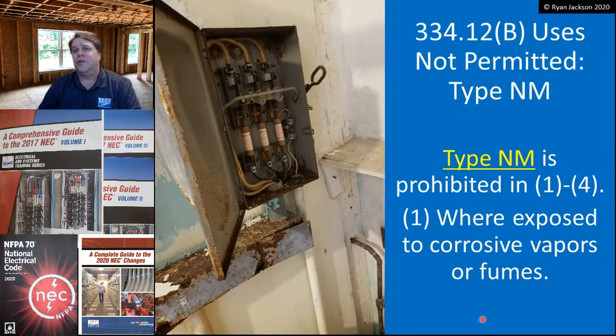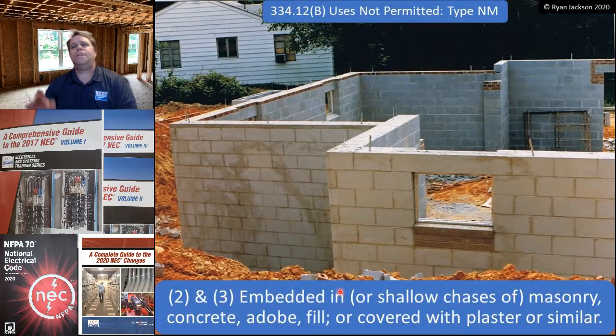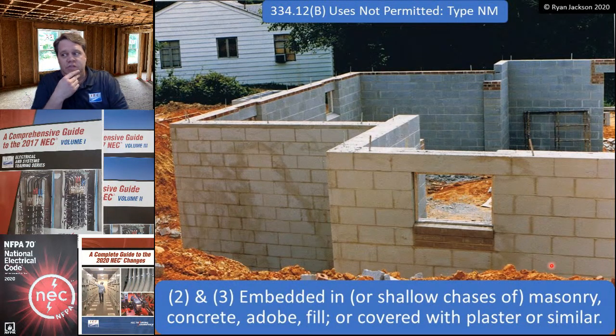One thing that we are figuring out is that they're toxic as far as corrosion is concerned. This is a swimming pool equipment room, and you can see it's corroded away to nothing. Cannot use NM cable in such a location. For NM, not NMC, but NM, you also cannot embed it in shallow chases of masonry, concrete, adobe, fill, or covered with plaster or similar.